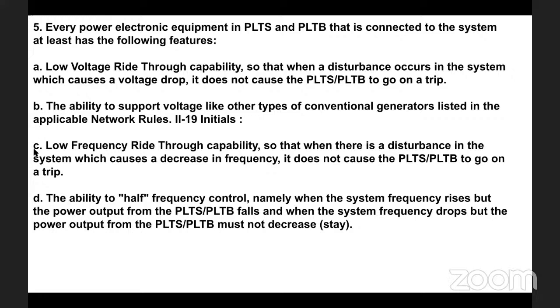low frequency ride-through capability, so that when there is a disturbance in the system which causes a decrease in frequency, it does not cause the PLTS, PLTB to trip. D, the ability to have frequency control, namely when the system frequency rises, the power output from the PLTS, PLTB falls, and when the system's frequency drops, the power output from the PLTS, PLTB must not decrease, but stay.